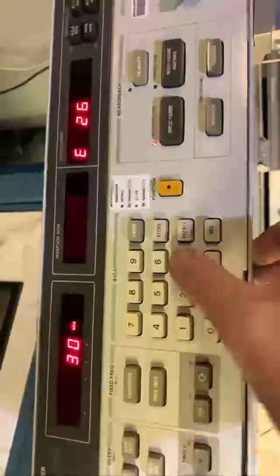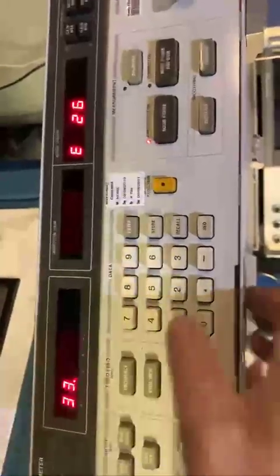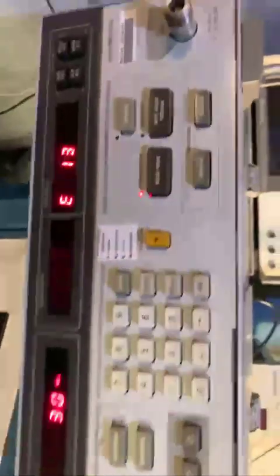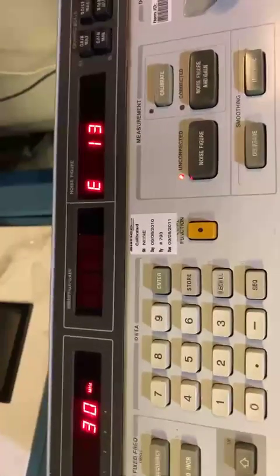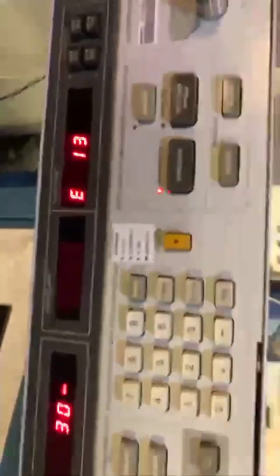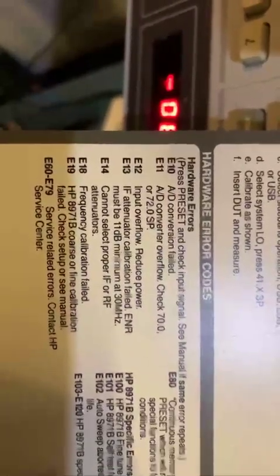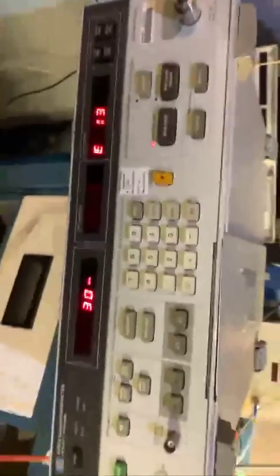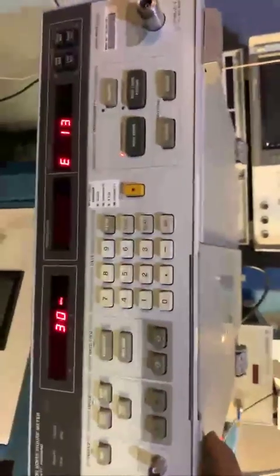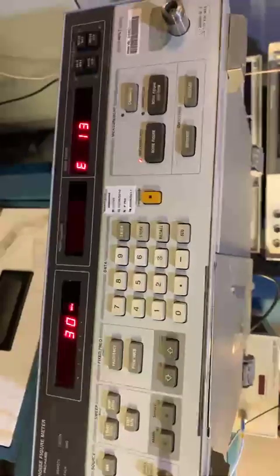33.1 special, and now you see it says IF cal. It fails with E13, which of course is because we don't have the noise source connected to it. And you see this right here, this E13 IF attenuator calibration failed. ENR must be 11 dB minimum at 30 megahertz, and of course we don't have a noise source connected here right now, so it's logical that this failed. But this is how you do it. This is how you cure this error.